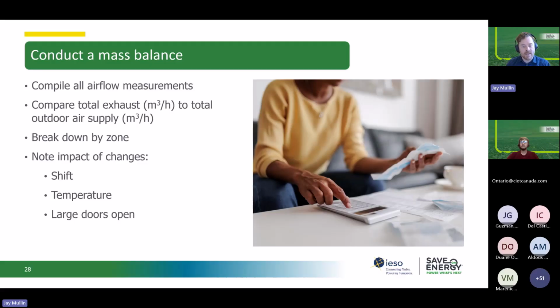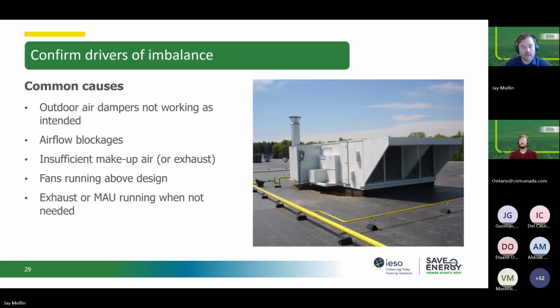And you want to get an understanding of what that mass balance looks like under different operating conditions, not just one, because it's going to be a dynamic system, right? As things change within your facility, that pressure differential, that pressure balancing is going to change with that, and you want to make sure you have the full understanding of it. With that information, that's when you want to start confirming what's driving that imbalance.